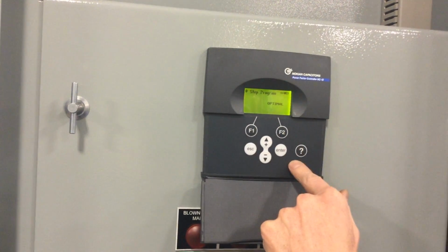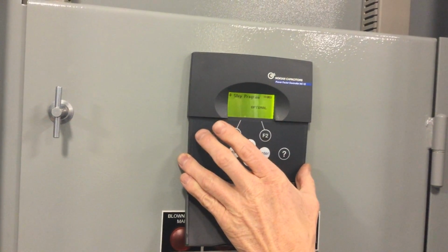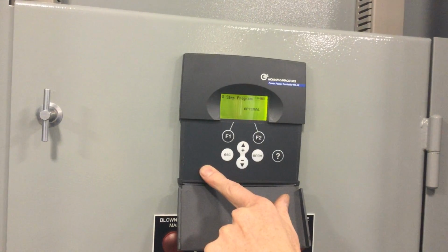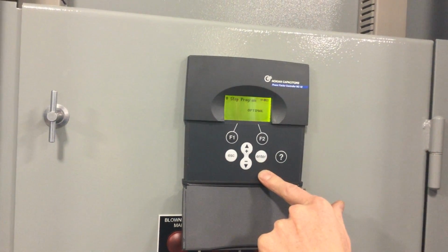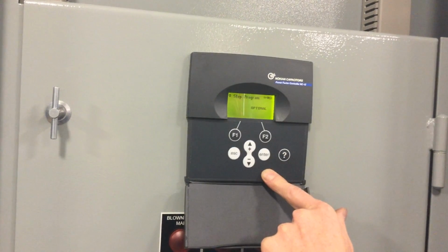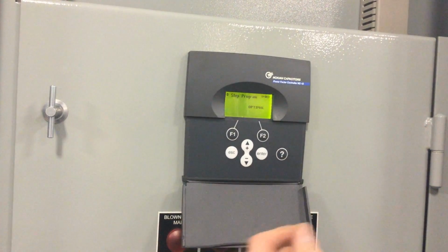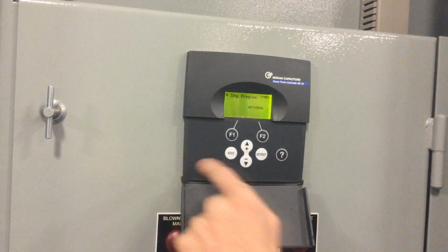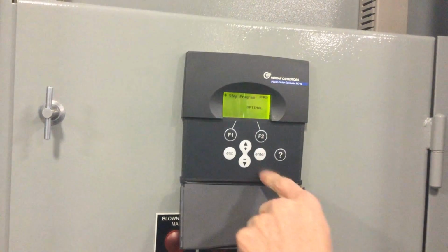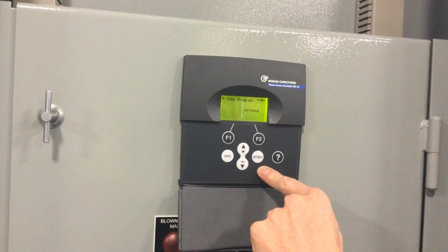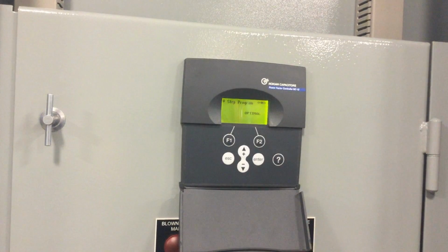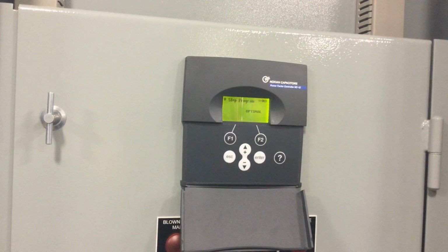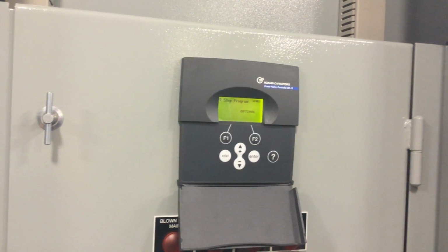Step program. This tells us how we want the controller to switch stages in. I won't go into the details of each program and how they work, but you can find that information in the Nokian capacitor operator's manual. And it determines, like I said, which stages will come on in which order, how quickly you get to your power factor, how evenly the switching is distributed between stages and so forth.